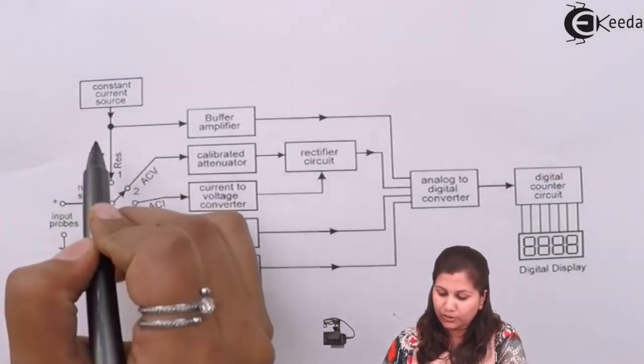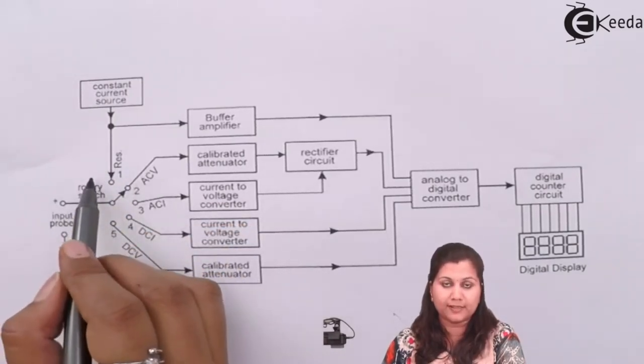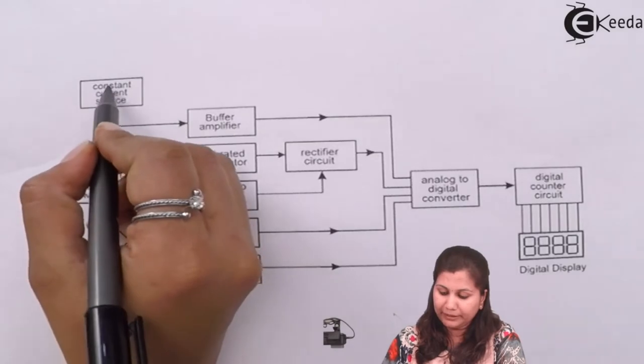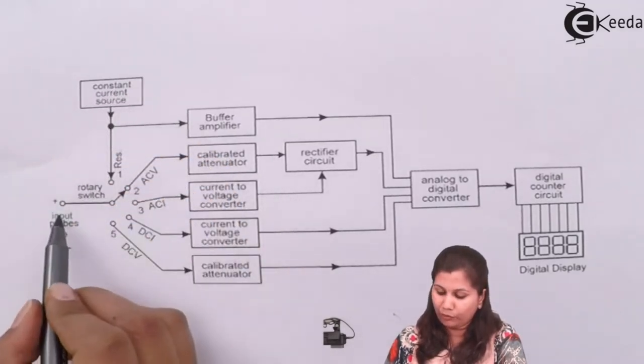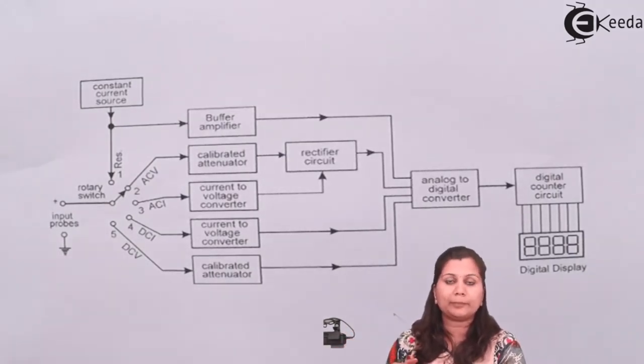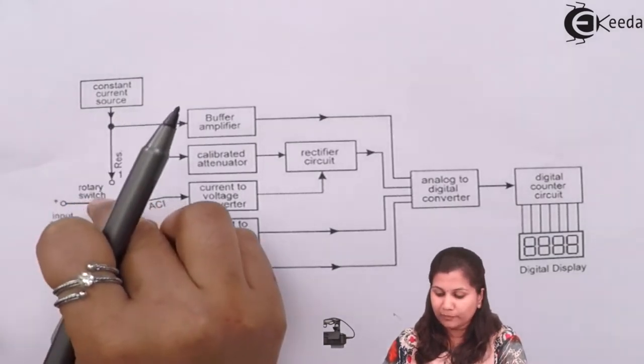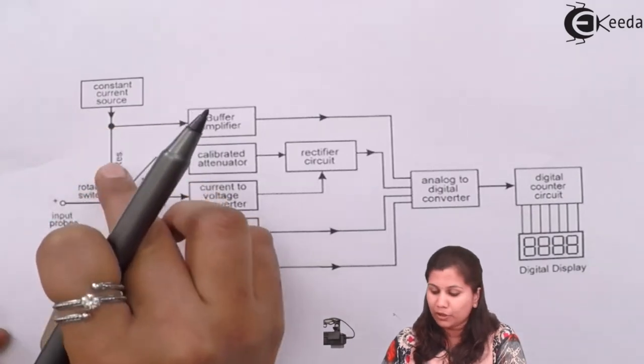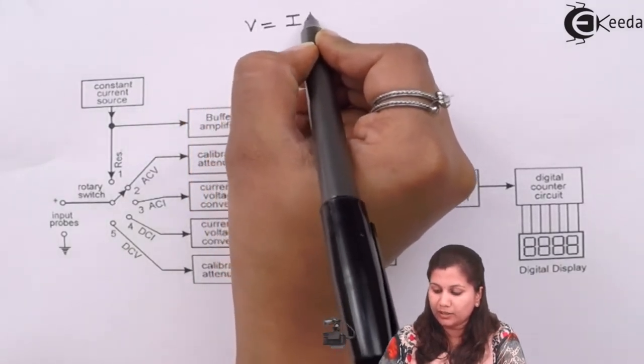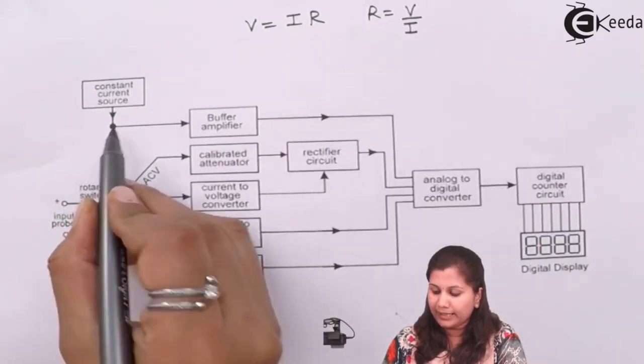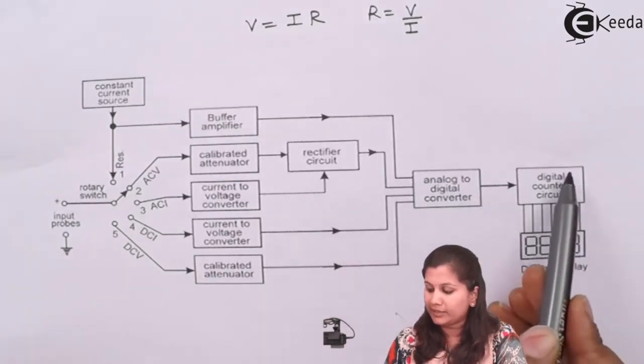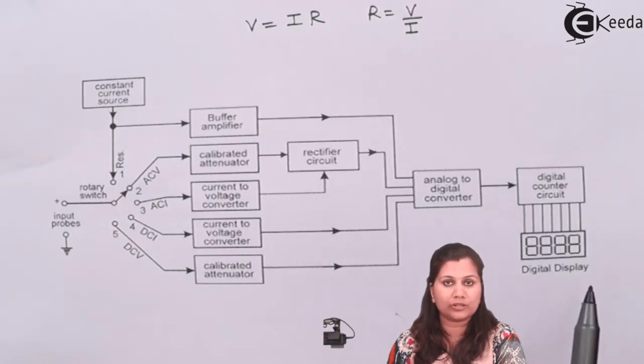We have here a constant current source, because when we want to measure resistance we need the value of voltage and current so that we can apply Ohm's law. So current will be given by this constant current source and voltage is provided from the power supply. So we can measure the resistance by applying Ohm's law: V equals IR, so R equals V by I. Then an amplifier is connected, which is going to amplify this signal, convert it into digital form, and give us a digital output on the LCD screen.